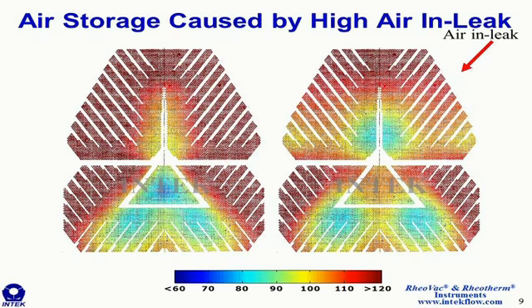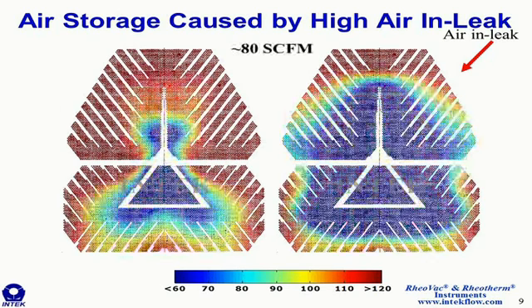And so the air in-leakage increased from 5 all the way up to about 80 SCFM. And this is the performance profile, the measured performance profile of this condenser with that higher air in-leakage. You can see 2 very large stagnant zones, a larger stagnant zone in the B shell because it's closer to the source of the air in-leakage, and most of it is going to that bundle. And you can see a large stagnant zone in the A shell as well. And so as I mentioned before, the way to recover this performance is to reduce the air in-leakage or increase the vacuum equipment capacity to return it to the original condition.